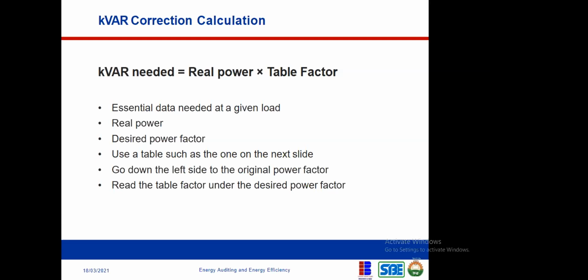That's how we correct a power factor problem, and that's what this section is going to talk about. How do you determine the size of capacitor that you have to put to correct your power factor? In correcting your power factor, you need to multiply your real power, that is the kilowatts or the watts, times a table factor. There's a table factor I'm going to show to you.